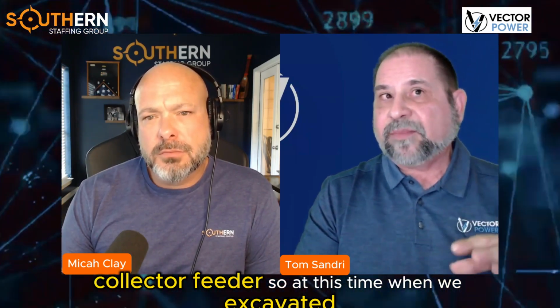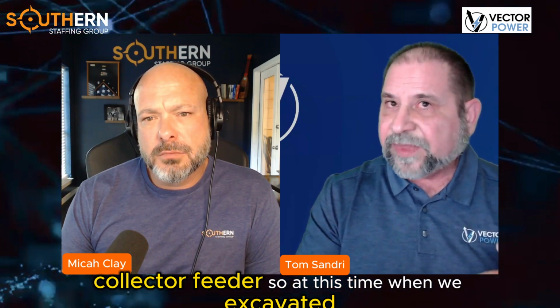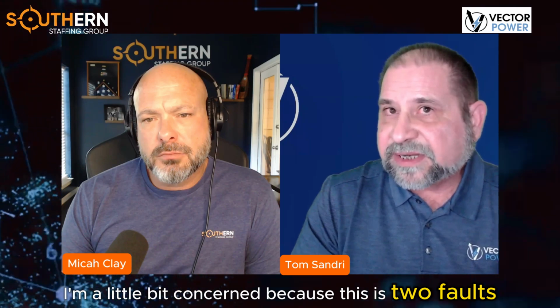At this time, when we excavated it, I said to the client, I'm a little bit concerned because this is two faults. The first one occurred 27 months after your acceptance test. The second fault happened 3 months from when we found the first, and again, it's in another splice.